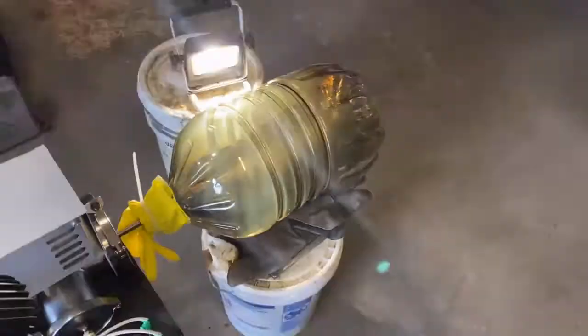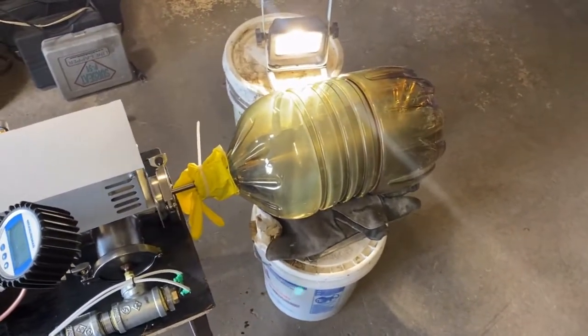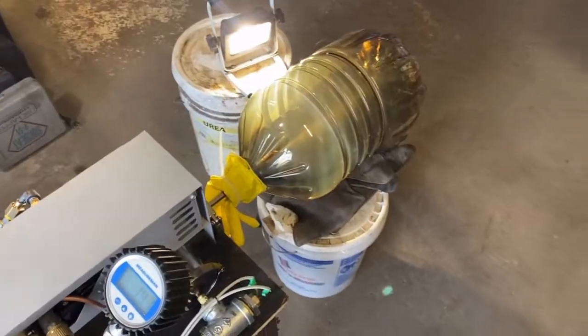You get these little jets, you see them waffling. See those fingers? We get this very erratic, hard-to-use spray pattern. This would still work just fine in most furnaces, but we want performance — we need the highest heat possible.